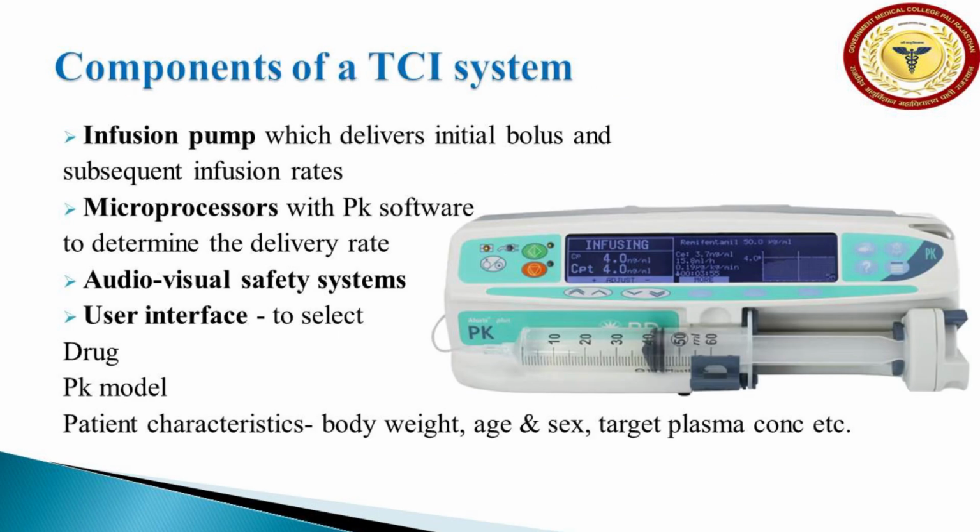Components of TCI: an infusion pump, which delivers the initial bolus and subsequent infusion rates, and microprocessors with pharmacokinetic software to determine the delivery rate, an audio-visual safety system, and a user interface to select the drug, pharmacokinetic model, patient characteristics like body weight, age, sex, and target plasma concentration.